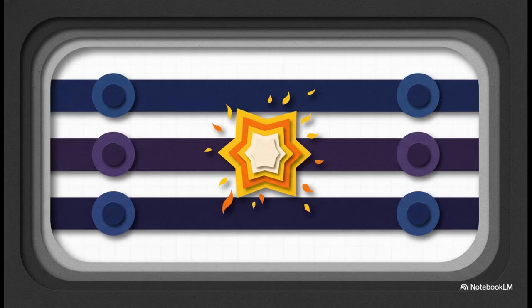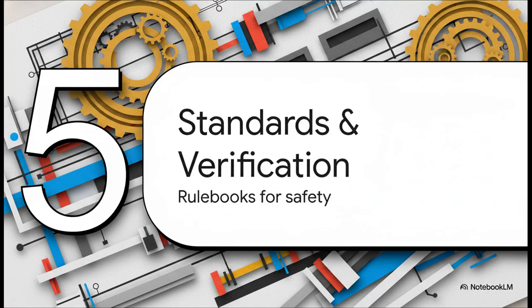But even with a flawless installation, things can loosen up over time. That is exactly why infrared thermography is widely treated as the modern hero of electrical maintenance. Periodic IR inspections under a meaningful load allow technicians to actually see the invisible hotspots forming at failing joints or overloaded sections. It's a real game changer because it lets them fix the issue long before it triggers a catastrophic shutdown or an arc flash event. And finally, Section 5, Standards and Verification. The rule books that keep us safe.